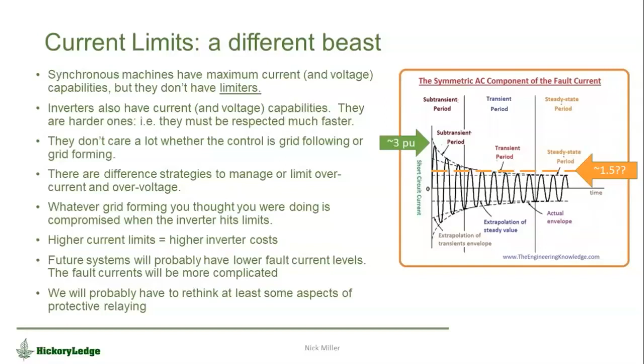This is ground that's going to be important for the industry: how we handle overcurrents on grid forming inverters, how much money we throw at increasing their current carrying capability, and what the implications are relative to adding costs and compromising current, and I'll use the pejorative, old-fashioned protective practices. Less fault current means protective practices may need to evolve or be replaced. Spending huge amounts of money to protect decades-old protective practices is something that needs to be challenged—that's my editorial opinion.